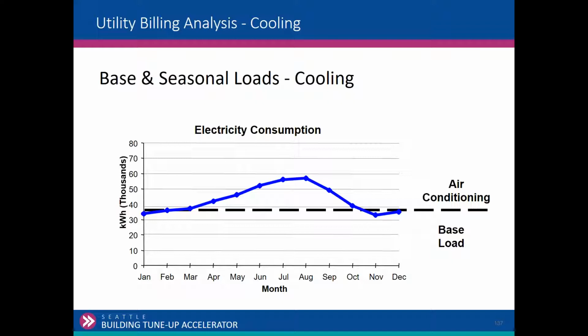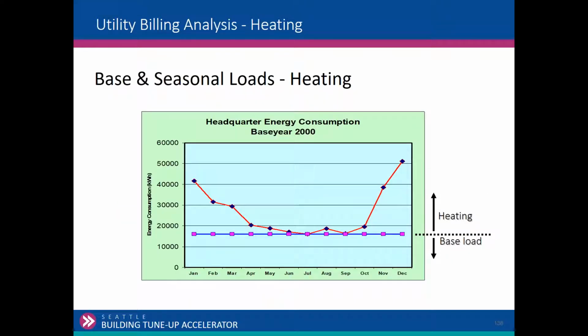So we do ask questions about what percentage, a little bit of a disaggregation of the energy use, just for heating and cooling purposes. Don't spend a lot of time on it. Make an estimate of the building analysis. You've got the building information in the portfolio manager. You can export that data, do a quick analysis, done. Same thing on the heating side. If you do have base loads on heating, hot water, gas equipment, another seasonal analysis and do an estimate of heating loads.